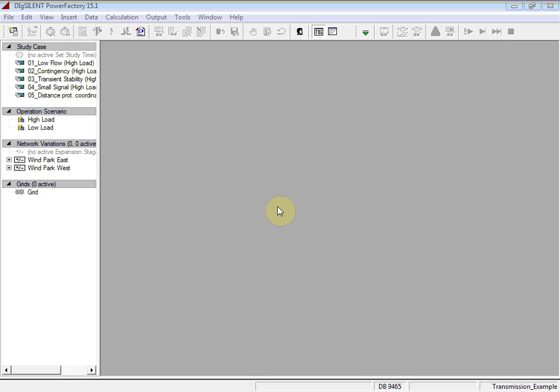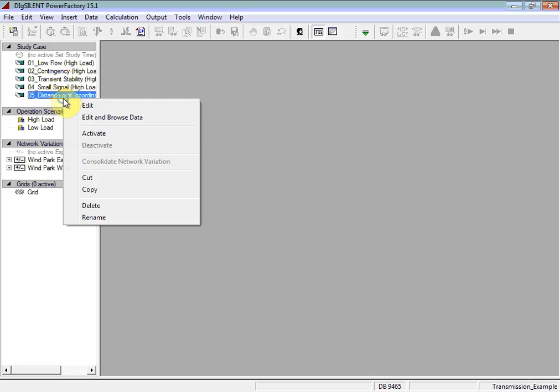In this example, we will demonstrate the functionality of the Distance Protection Coordination Assistant. This tool is used to automatically calculate zone reach settings for distance protection relays. The settings which are calculated depend on the network topology as well as a set of rules for which the user can define parameters. Activate the study case number 5, Distance Protection Coordination Assistant.